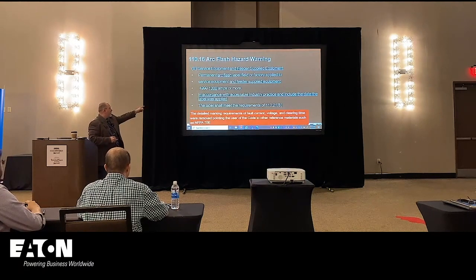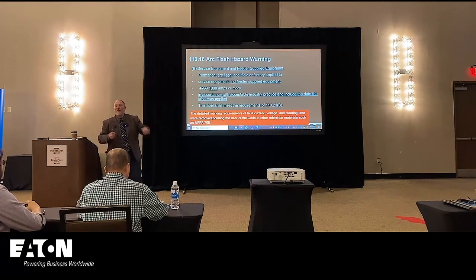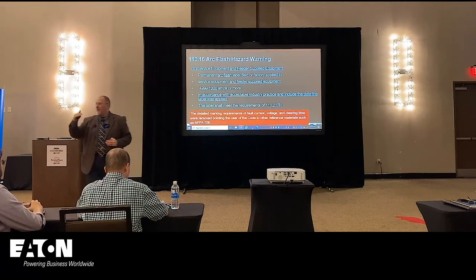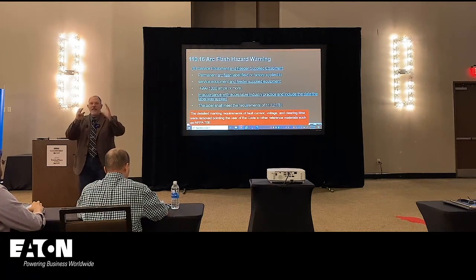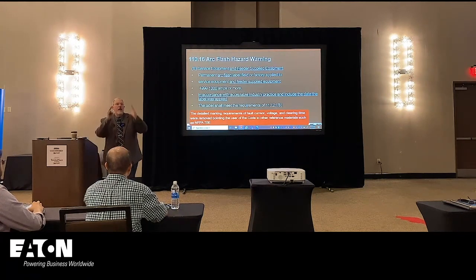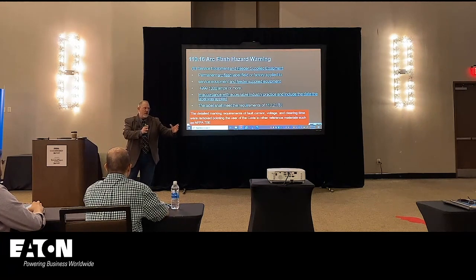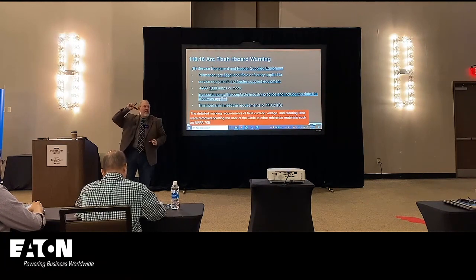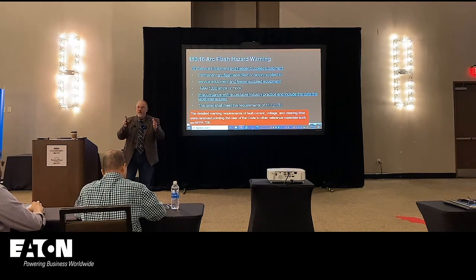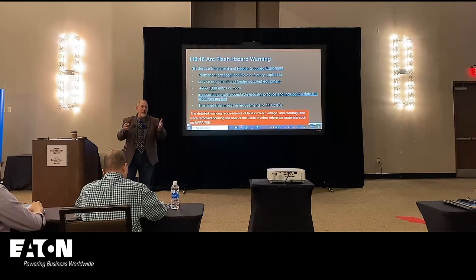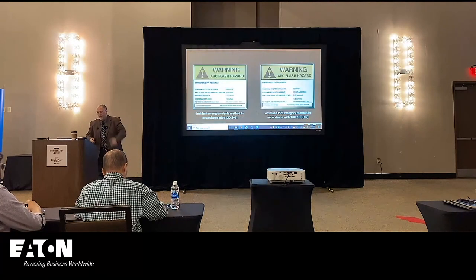There's where we took the 1,000 and in accordance with acceptable industry practice. So what we removed out of here, remember, we had the voltage, we had the clearing time of the service overcurrent device, all that jazz. That lined up with 70E's PPE category method. But when you're at the service, you can't use the category method at the service because your protecting overcurrent device is on the utility. And if you dressed based upon the PPE category method, you would be underdressed for that application. We know service equipment is very high incident energy. So be mindful of that.